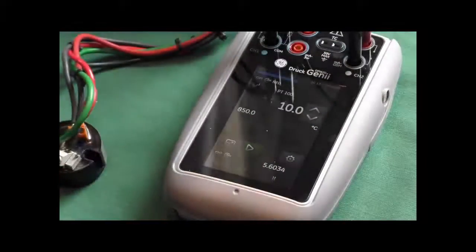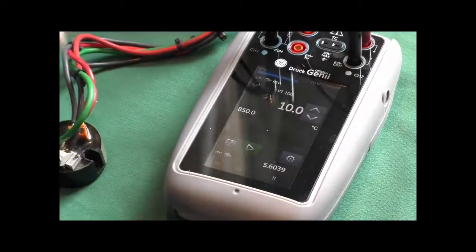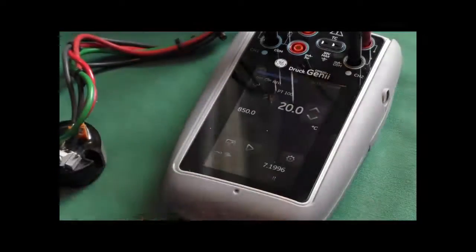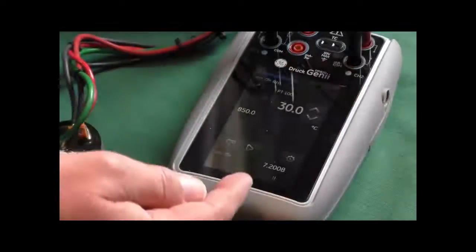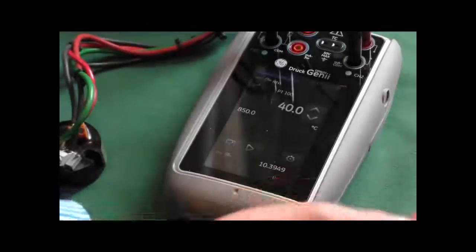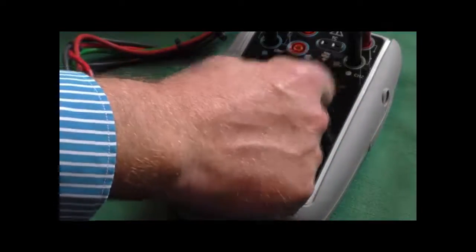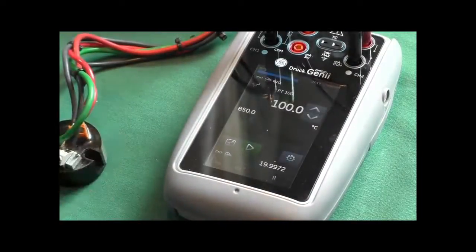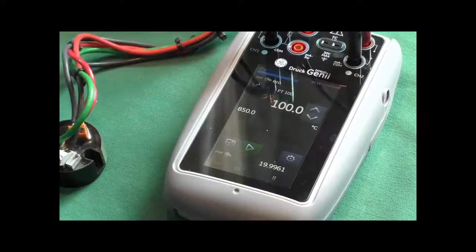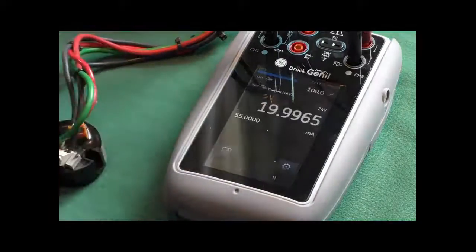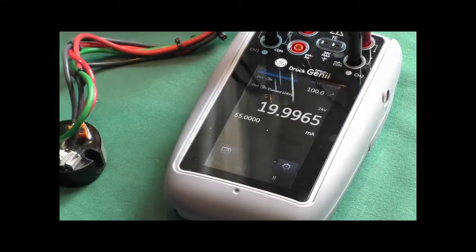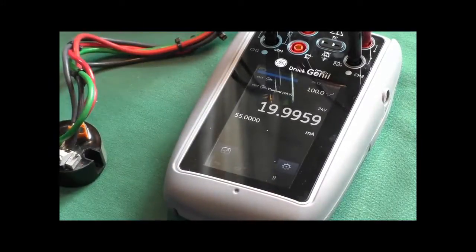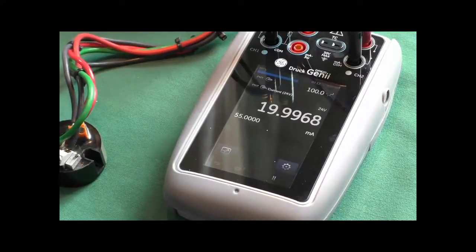And as we go up now, it's 0 to 100, so every 10% is 10 degrees C. I can quickly step through, check the milliamps output at the bottom. So we're going up to 30, 40, 50, so nearly our 12 milliamps, and so on, right up to 100%, 20 milliamps. In fact, it's set very close and it's well within tolerance at the moment. Obviously, if I needed to adjust that, I can. I can also configure channel 2 to display the percentage error. It takes a little bit more time, but that can be done as well, so you can actually see how far out of spec the setting is on the RTD transmitter.